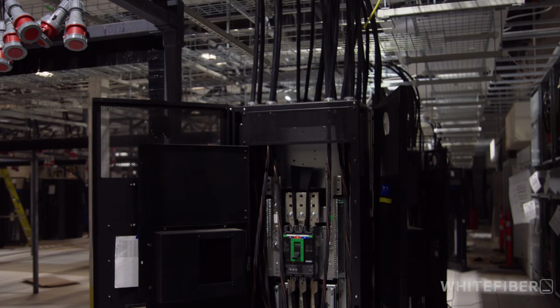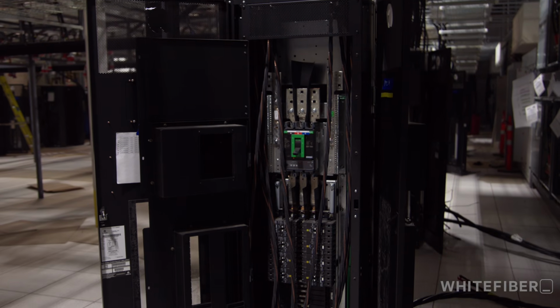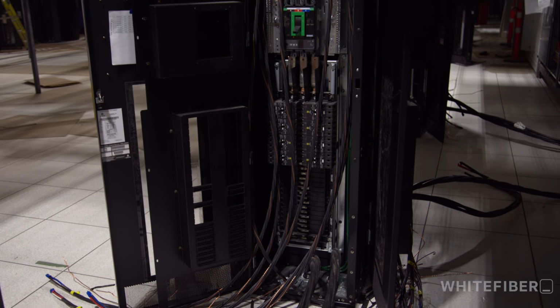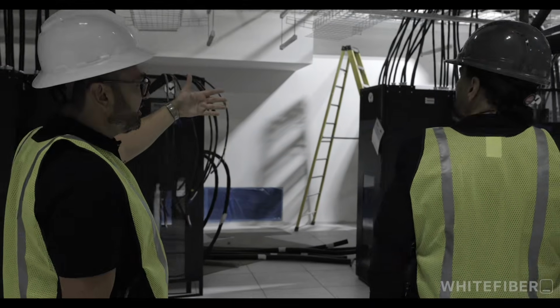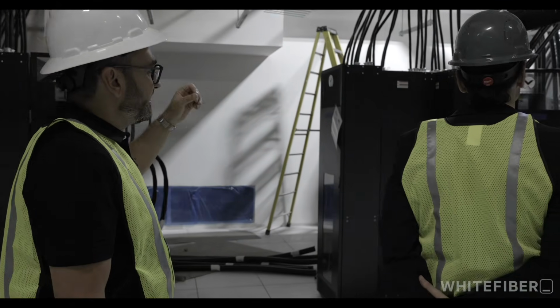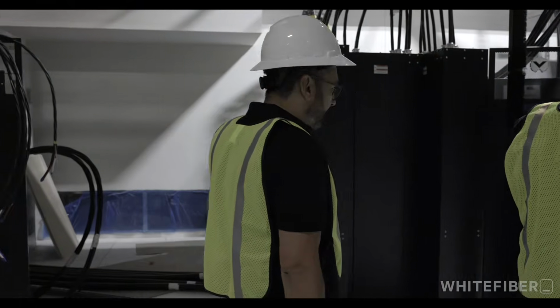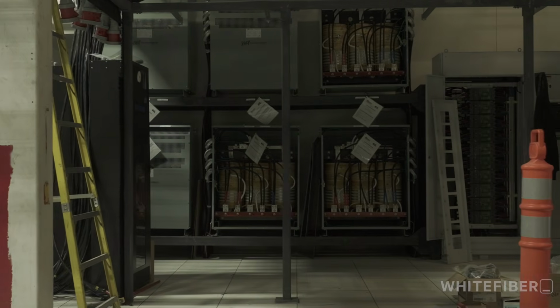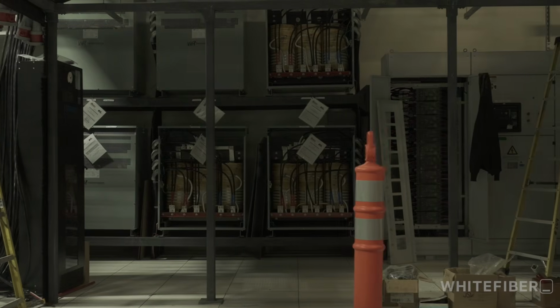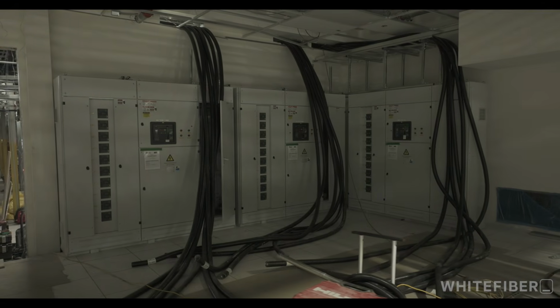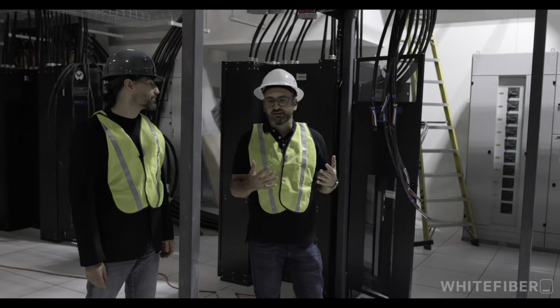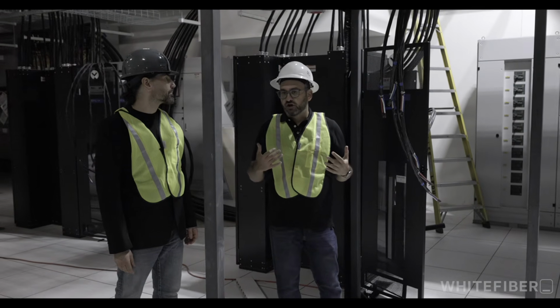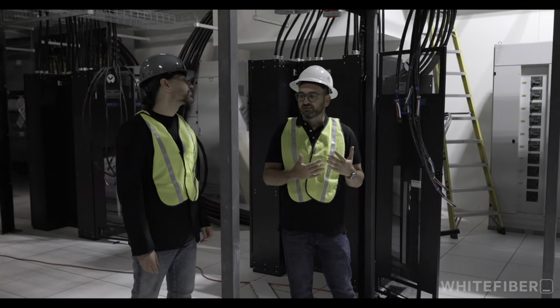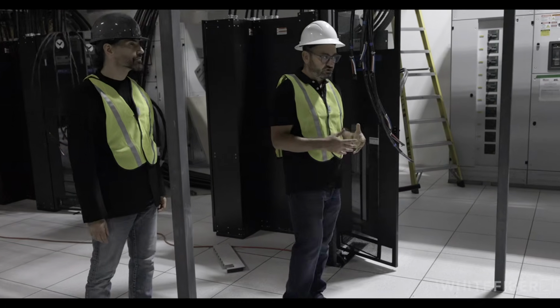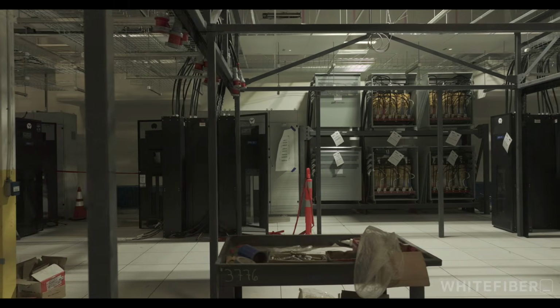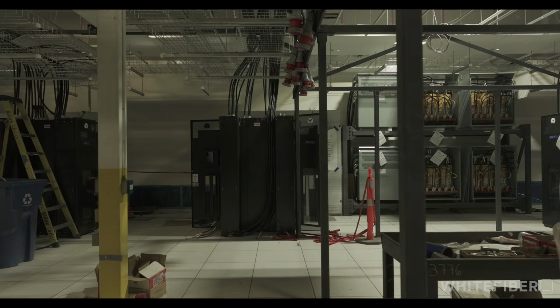So here we have the power distribution units. These black boxes are really what feeds each cabinet. And behind that, we got their transformers, getting them down to the right voltage. And next to those, we do have the output panels. So those are connected to UPS battery systems that are in place just for the 10 or 15 seconds of utility failure, the time it takes for the generators to kick in. So if there were to be a utility failure, the end user would not realize it because of the battery systems.